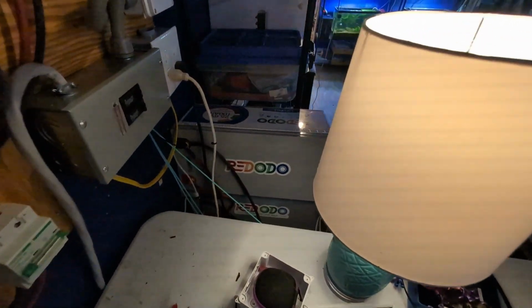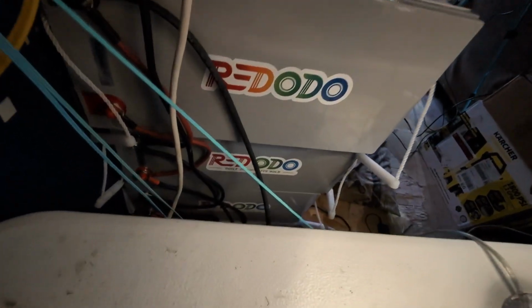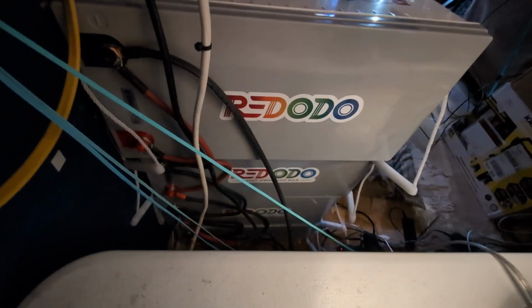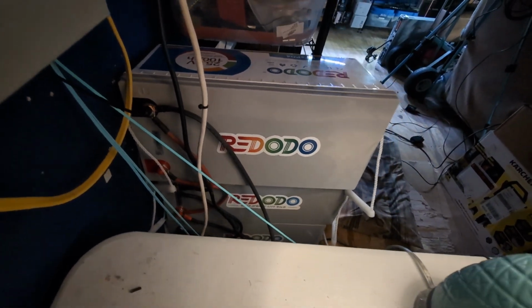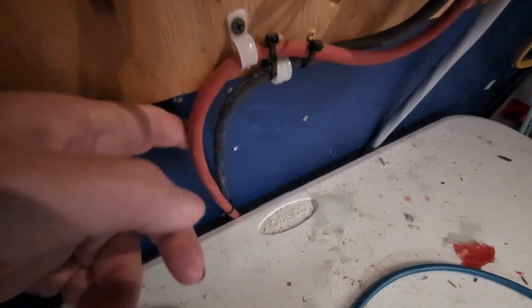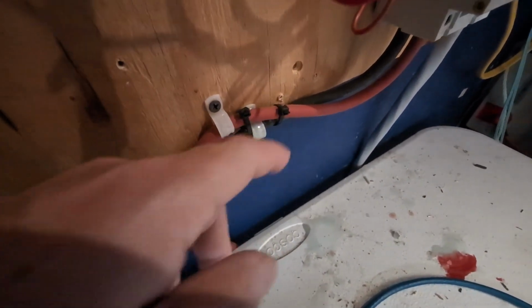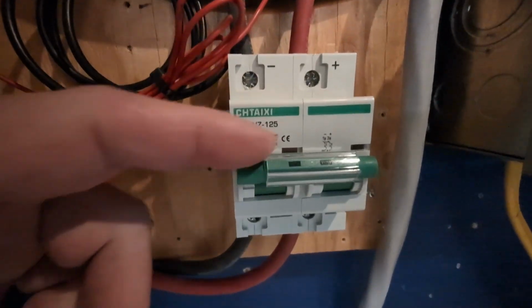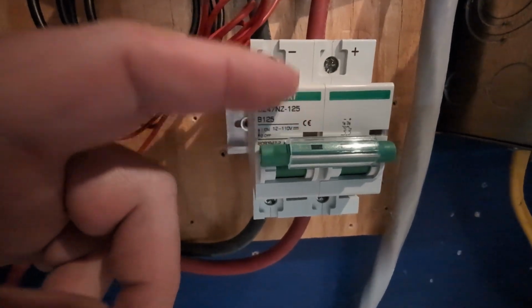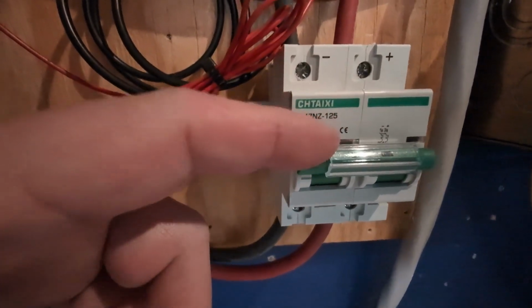So the batteries are now stacked here. I've got 4 of the Redodo 24 volt 100 amp hour batteries. There's 4 of them stacked. They're wired in parallel. And then those cables come up here. They're now secured and wire tied, just to keep them from moving, so they can't move anywhere. They go up to the bottom of this 125 amp breaker. And this is a DC breaker, it's green.